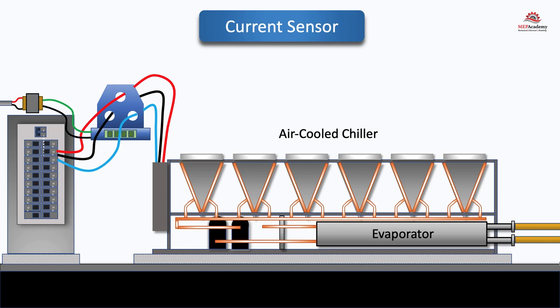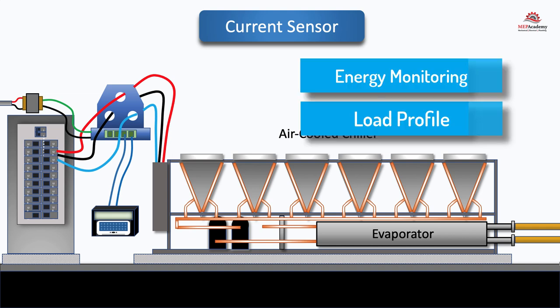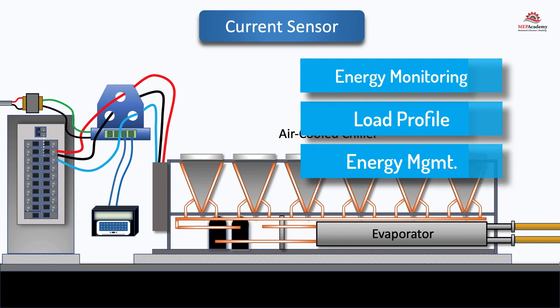This signal can be fed into a data acquisition system, energy meters, or control system for further processing and analysis. By continuously monitoring the current draw using the current sensor, the energy usage of the equipment can be calculated. The output signal from the current sensor can be processed and integrated over time to track the energy usage of the equipment. This information can be used for energy monitoring, load profiling, energy management, or billing purposes.